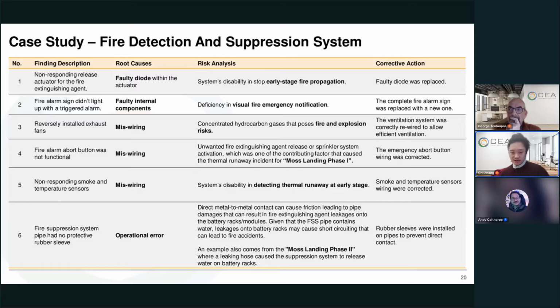It's worth mentioning that finding number 4, the failure in emergency abort function, and number 6, potential piping damage, are two of the contributing factors to the Moss Landing fire that happened years ago. This shows how important quality assurance can be in catching problems at the factory to avoid these tragedies. When suppliers' orders pile up and they are under time pressure to deliver, these quality problems can really come up.